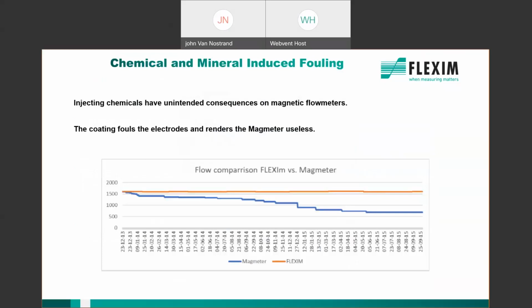What that does is it coats the magmeter electrodes. When you inject chemicals like orthophosphate, you see in this picture here, the blue line was a magnetic flow meter. In this case, it was a manganese coating, but orthophosphate has the exact same effect on it. The FLEXIM meter just shows a nice steady flow, where the magmeter over time begins to show lower readings, as much as 50% of the actual reading. So it is a real problem.